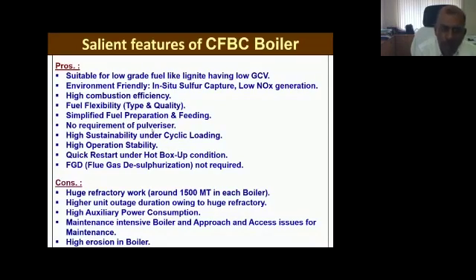Though there are these advantages, there is another disadvantage with this CFBC boiler. When we decided to go for CFBC technology and not a PF boiler, there is a huge cost to the company. Because of tonnage, a 125 megawatt boiler itself is 12,500 tons of total boiler tonnage. In that, 1,500 metric tons is refractory in each boiler. And this refractory, though it had an advantage on the operational side, on the maintenance side is a great disadvantage and creating a lot of challenges for us.